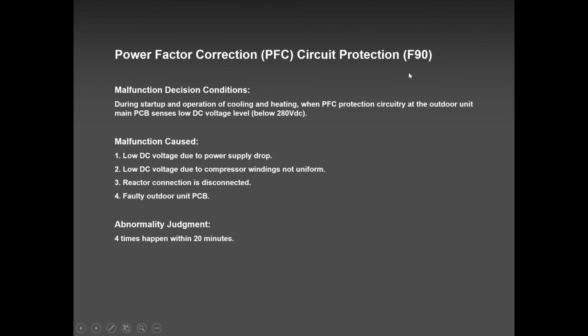F90. F90 is what? Power factor correction. Okay? Low DC voltage. So when you have an F90, in most cases, it's the outdoor PCB. I may have got 1 or 2 cases, but very rare. And honestly, it's not the compressor, it's the board.